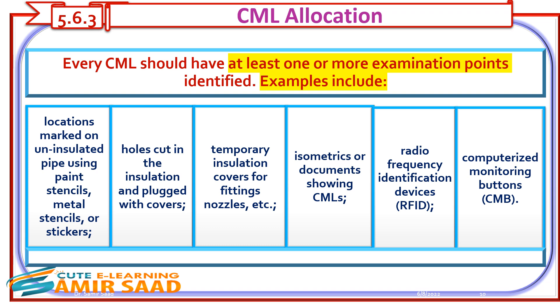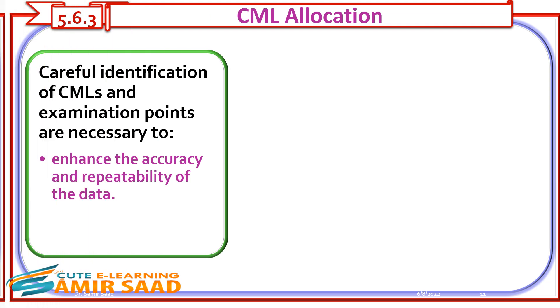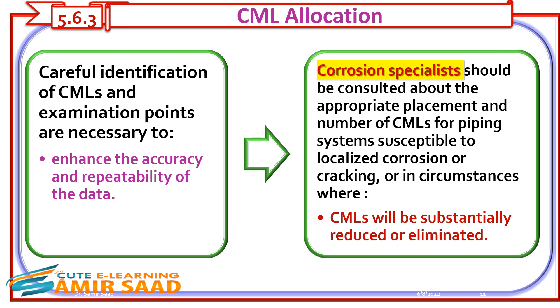Examples of examination point identification include: locations marked on uninsulated pipe using paint stencils, metal stencils, or stickers; holes cut in the insulation and plugged with covers; temporary insulation covers for fittings, nozzles, etc.; isometrics or documents showing CMLs; radio frequency identification devices (RFID); and computerized monitoring buttons (CMB). Careful identification of CMLs and examination points is necessary to enhance the accuracy and repeatability of the data. Corrosion specialists should be consulted about appropriate placement and number of CMLs for piping systems susceptible to localized corrosion, cracking, or where CMLs will be substantially reduced or eliminated.